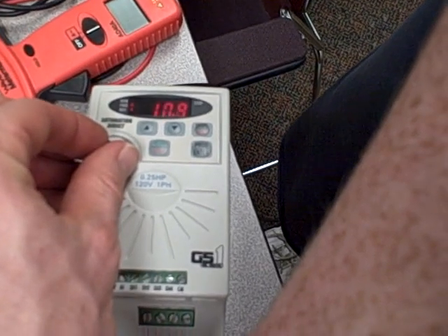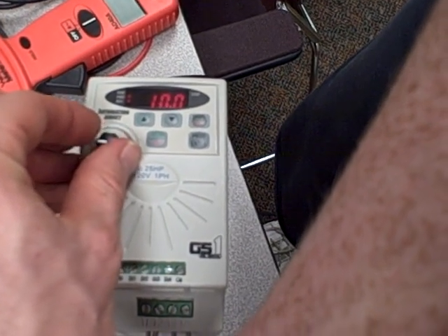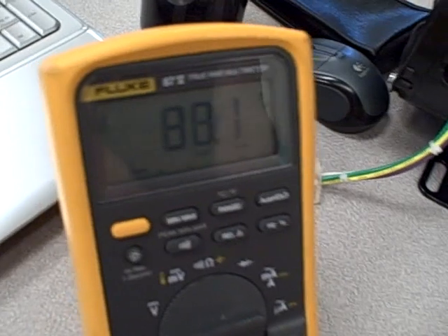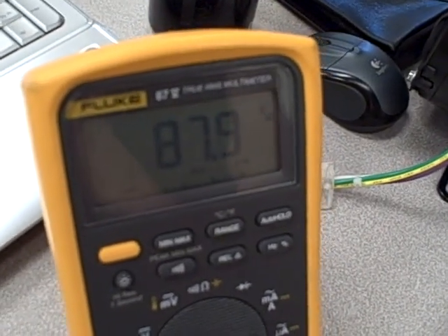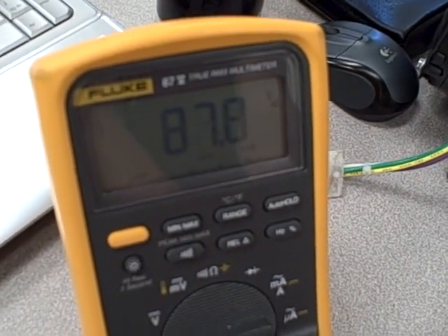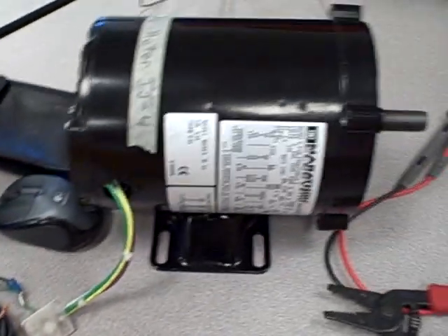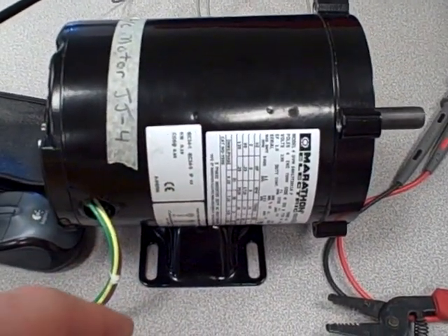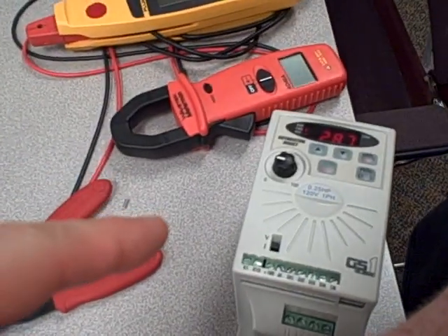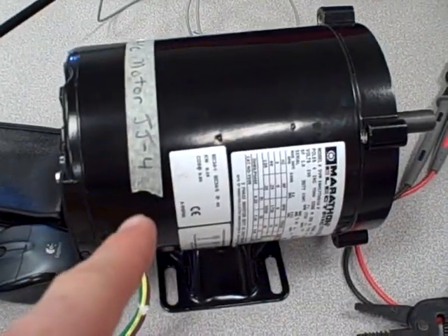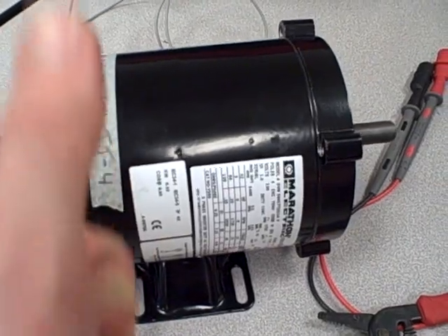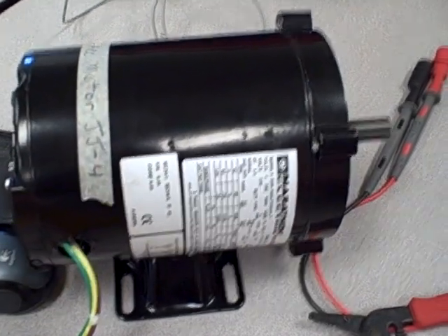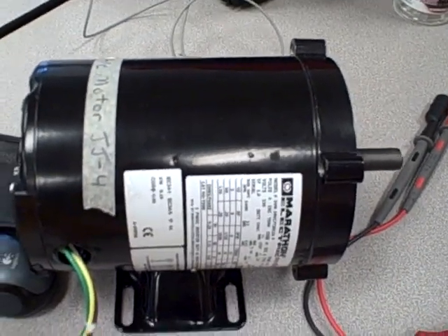Of course, the frequency is primarily what drives a motor at different speeds, but we have to reduce the voltage as well with frequency so that we don't overpower the windings of the motor at those lower frequencies. As we decrease frequency to the motor, the inductive reactance of the motor windings decreases as well. If this were to maintain a constant voltage output with a decreased reactance, that would result in vastly increased currents at low speeds, and that could burn the motor up potentially, or saturate the windings.